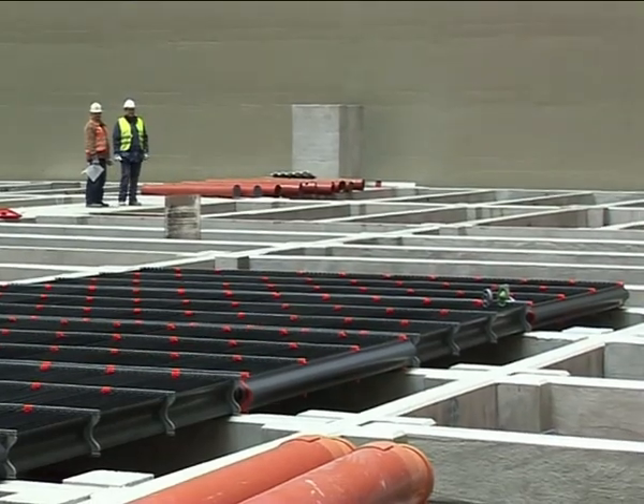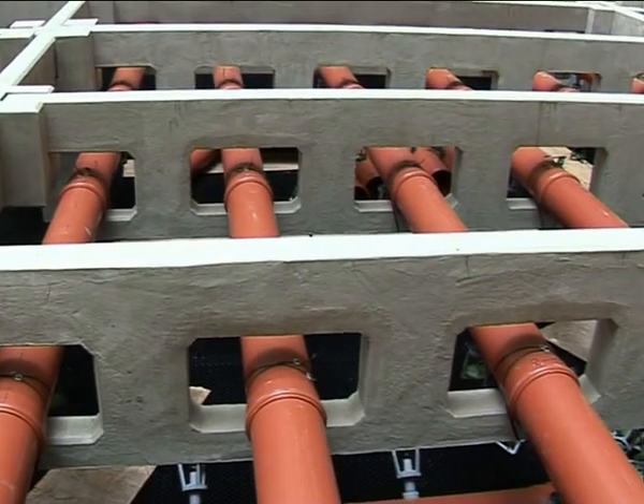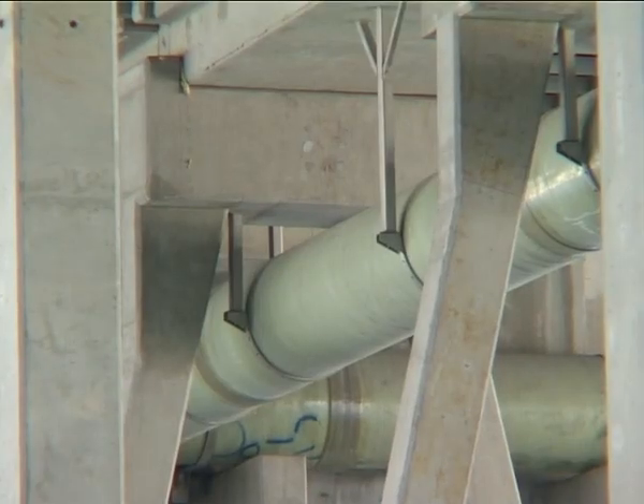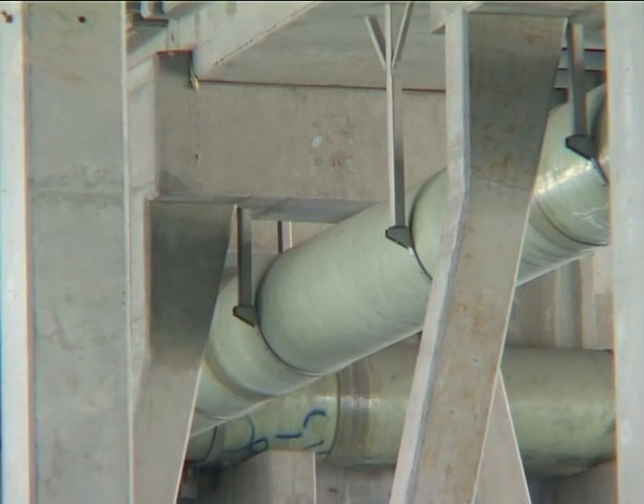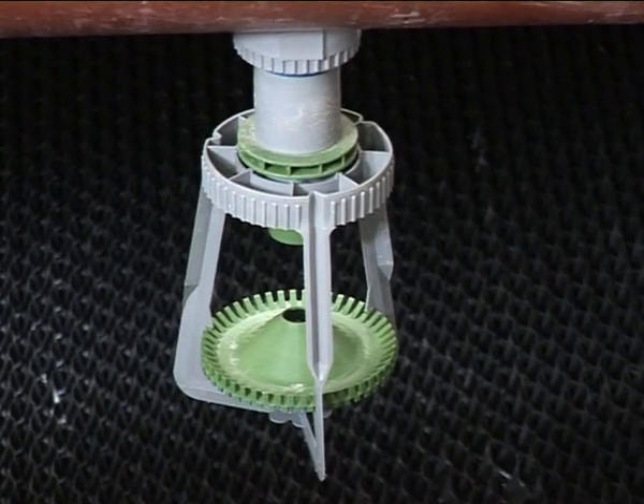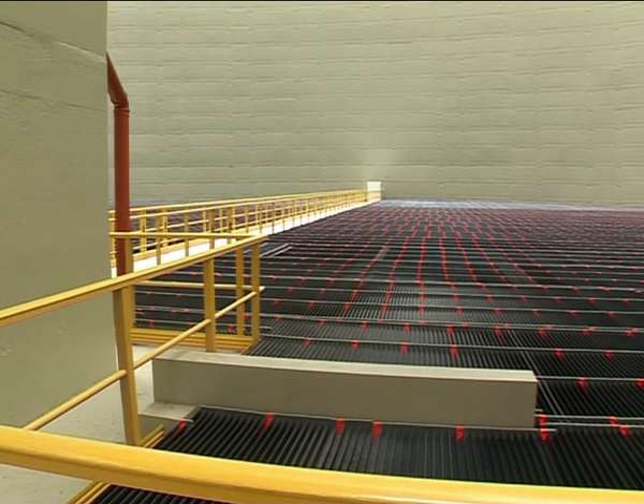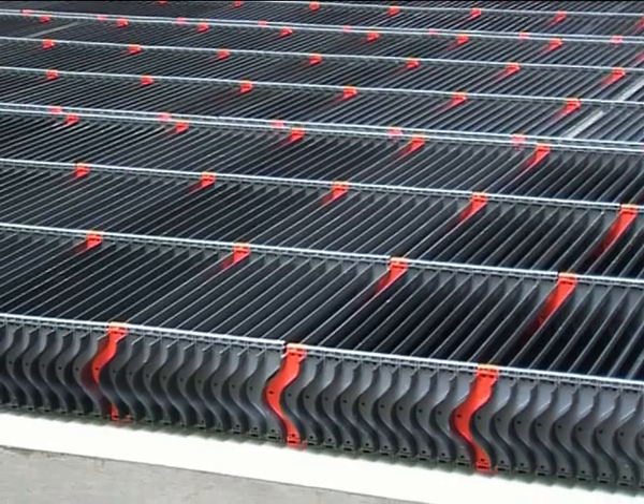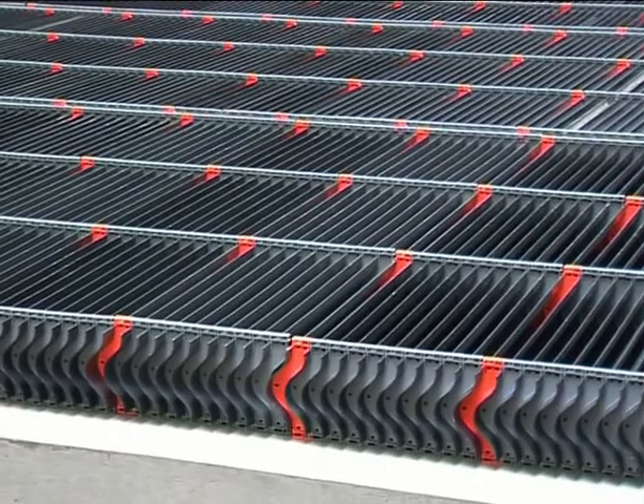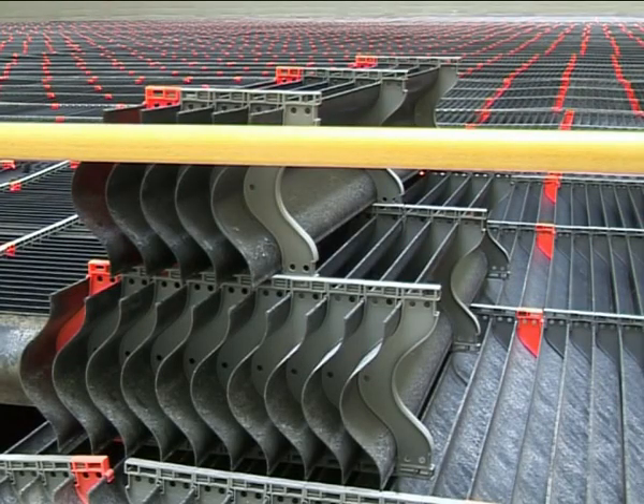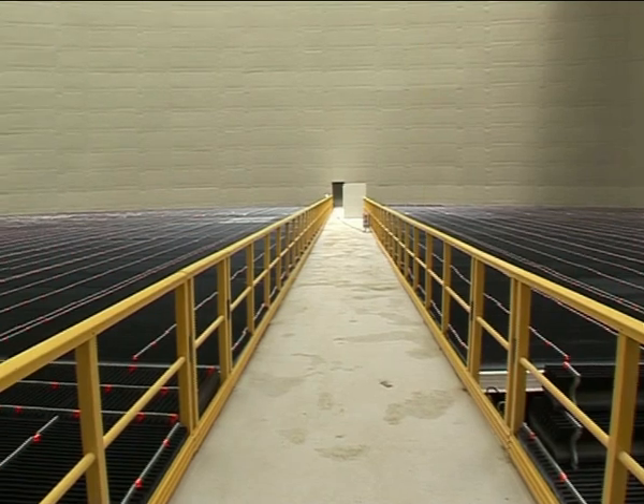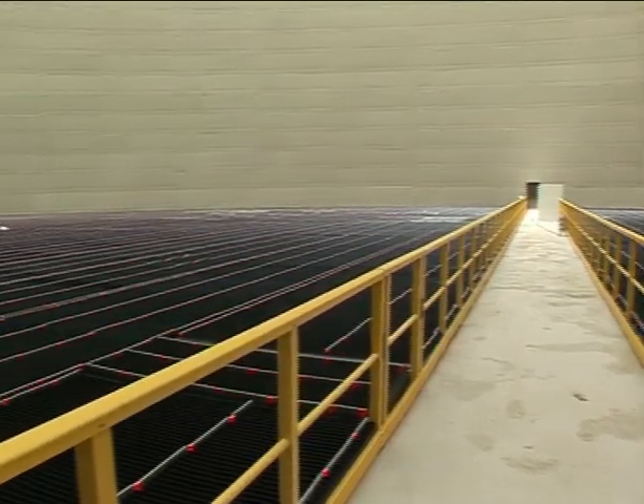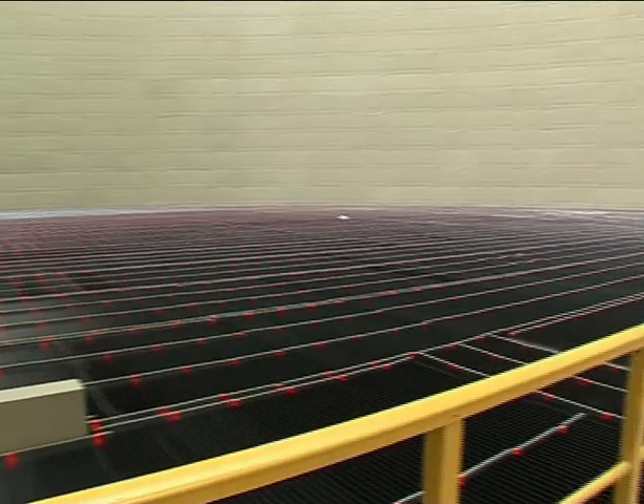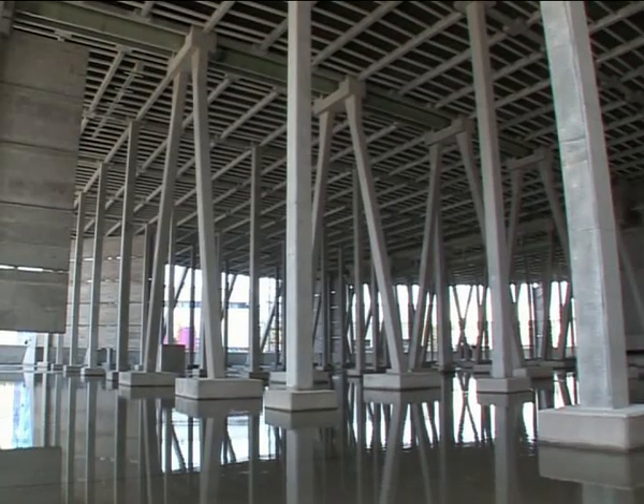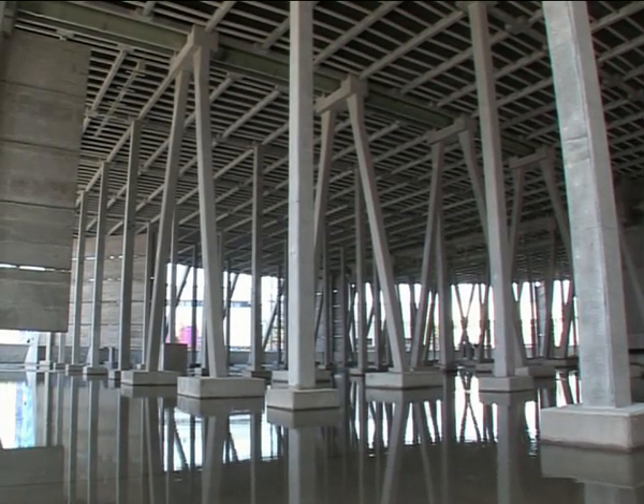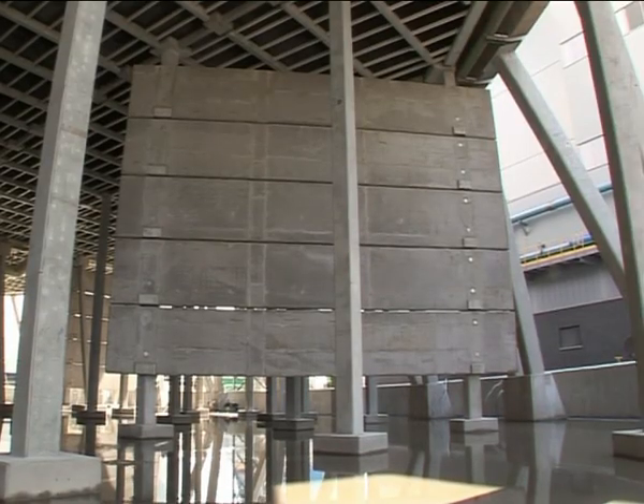Approximately 7 kilometers of plastic pipes with diameters ranging from 250 to 500 millimeters are in place at the sprinkling level, where more than 5,500 sprinklers are fitted. The upper side of the cooling system is covered with a drift eliminator made of specially shaped tiles. The cooling filling, 1.8 meters thick, is underneath. The cubic capacity of the entire filling is 14,000 cubic meters. 8 10-meter high reinforced concrete wind baffles were constructed under the cooling system at floor level.